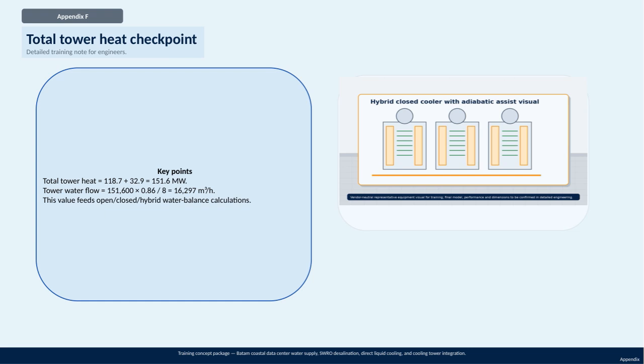engineering team's training. This section is part of our comprehensive training concept package that covers multiple components, including the Batam Coastal Data Center's water supply, SWRO desalination, direct liquid cooling, and how the cooling tower integrates into the system. Now let's break down the key points. The total tower heat is calculated as 118.7 plus 32.9, which gives us 151.6 megawatts. This value is essential because it represents the amount of heat the cooling tower needs to dissipate.